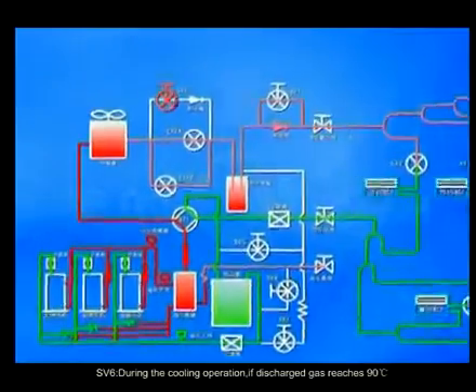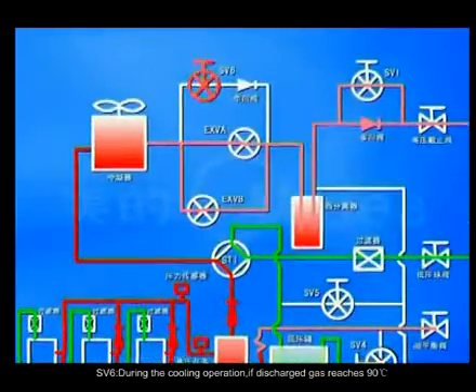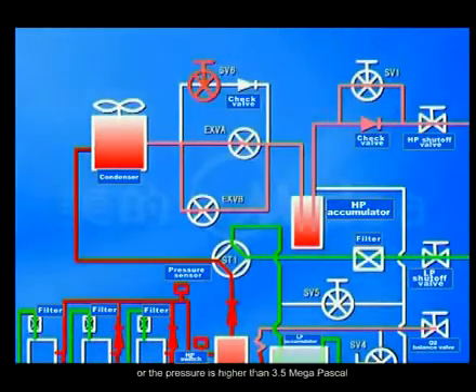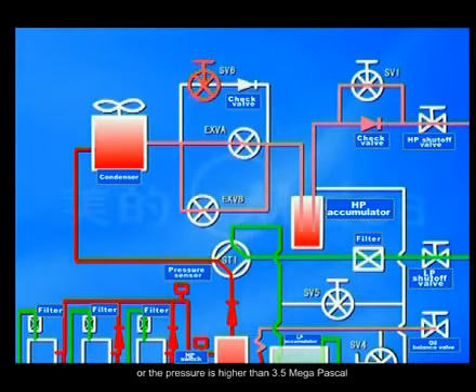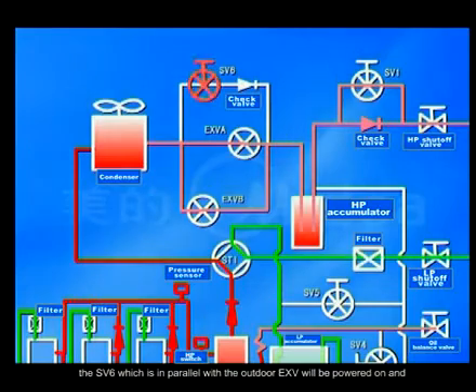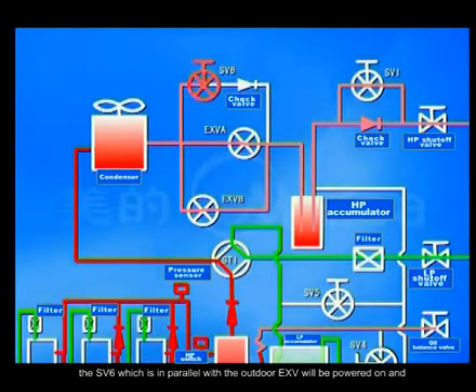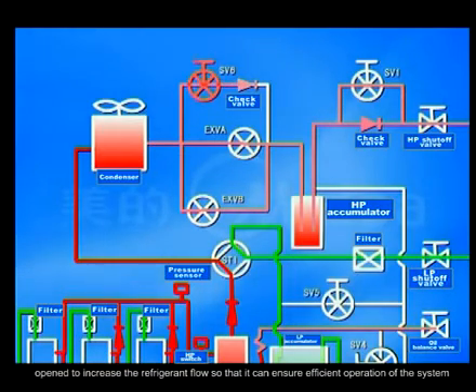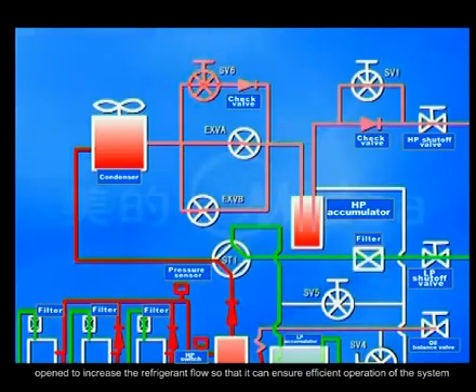SV6. During the cooling operation, if discharged gas reaches 90 degrees Celsius or the pressure is higher than 3.5 megapascal, the SV6, which is in parallel with the outdoor EXV, will be powered on and opened to increase the refrigerant flow so that it can ensure efficient operation of the system.